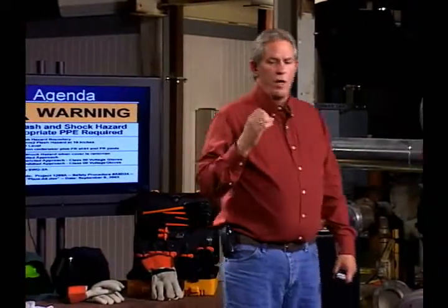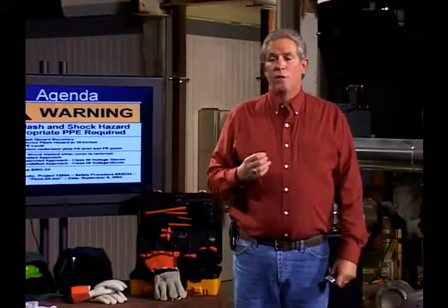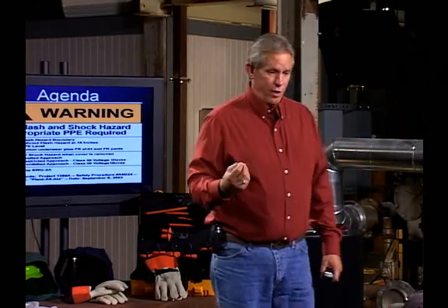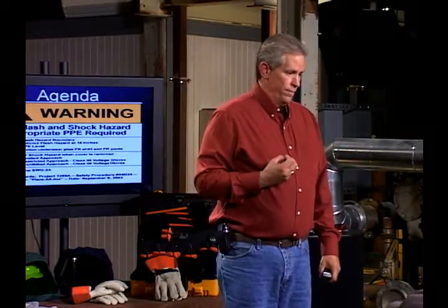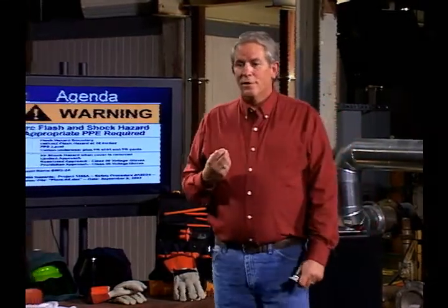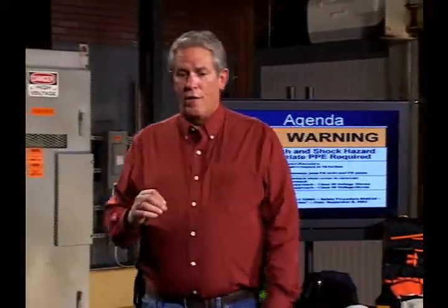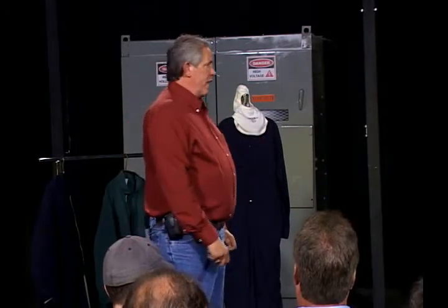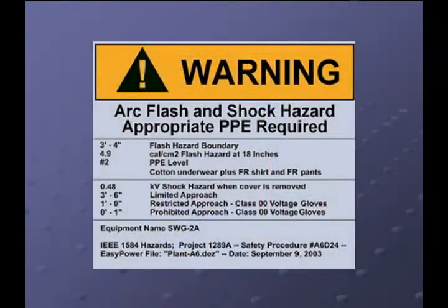But at that 4.9, just a minute ago I said 1.5 was enough to burn us to third degree. So what can 4.9 do? Okay. So we have to wear clothing that says in the label of the clothing that it meets or exceeds that 4.9. Now the NFPA 70E has set up categories for us where we know what the calorie ratings are based on the hazard risk category of the NFPA 70E, and they've really made it quite simple for us to follow.